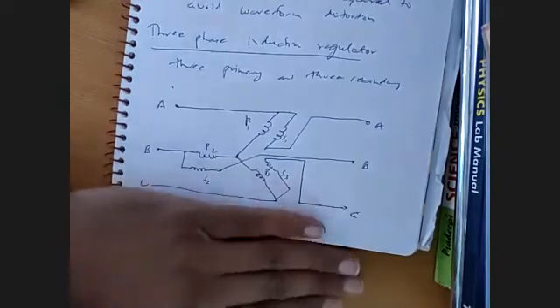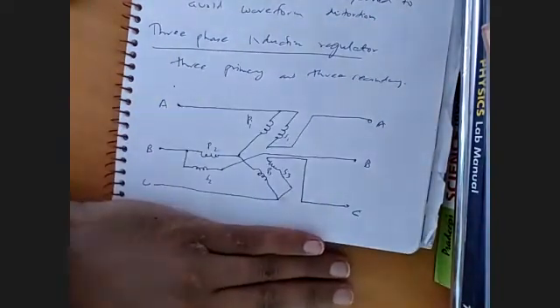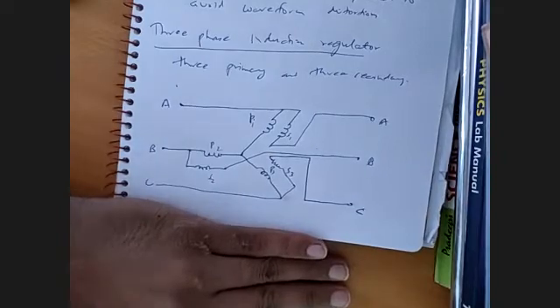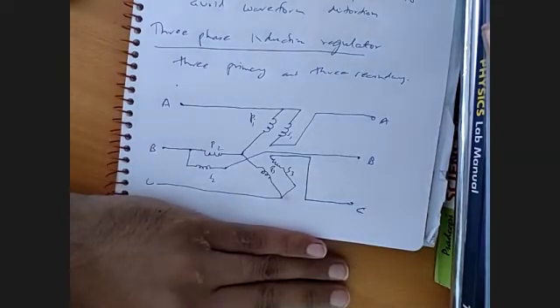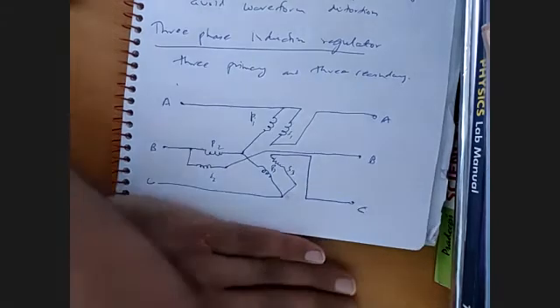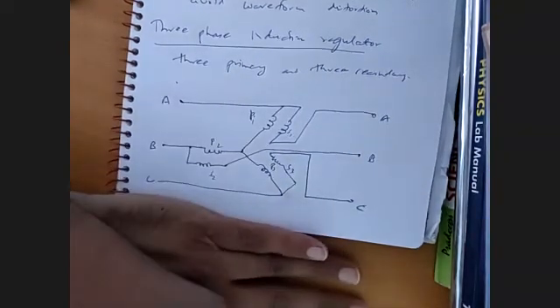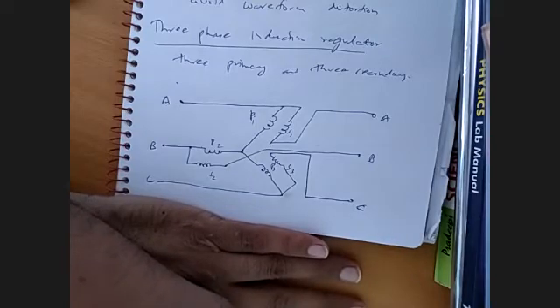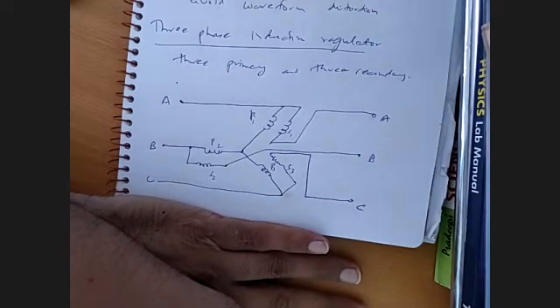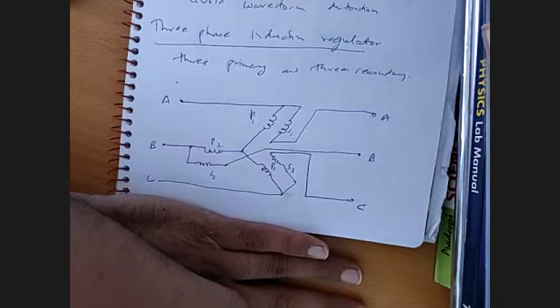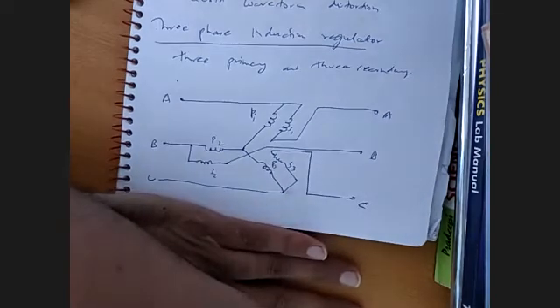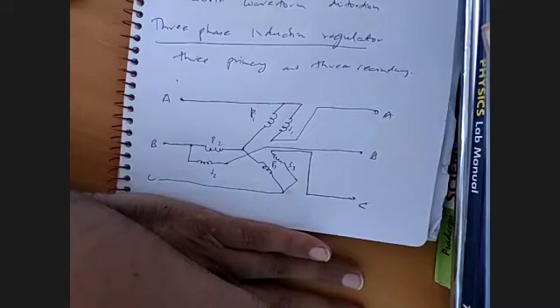So when we are talking about three phase, it is three windings only which are connected in star, and the regulator does not require any primary and compensating windings because the secondary winding of the regulator is magnetically coupled to one or more primary windings of the regulator. The rotating magnetic field of constant magnitude is produced, due to which the voltage induced in the secondary is of constant magnitude. The phase of the regulator varies with the change in the position of the stator.